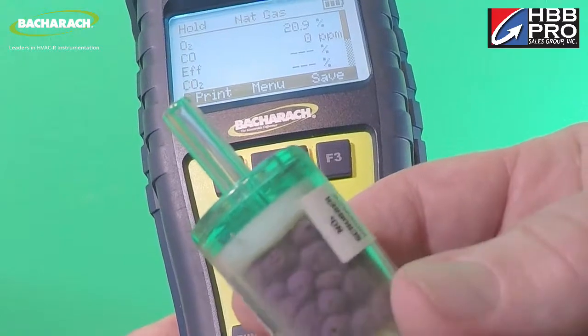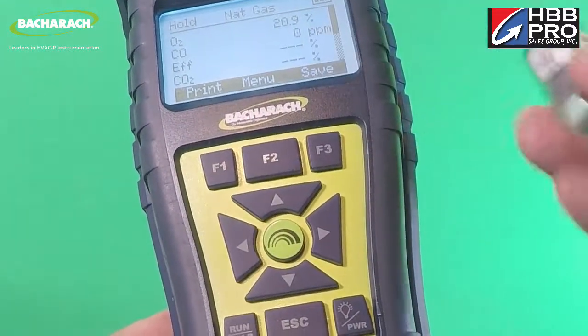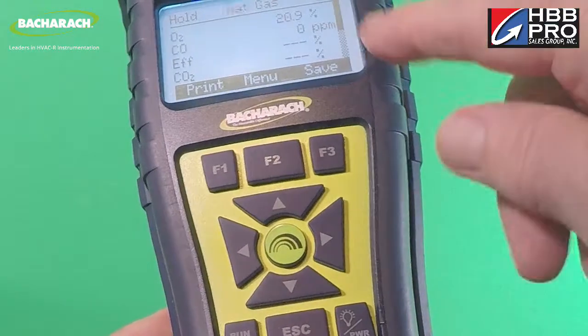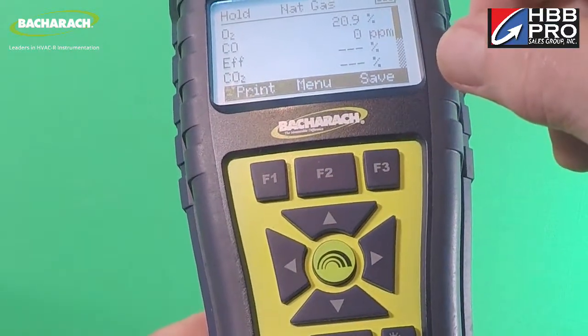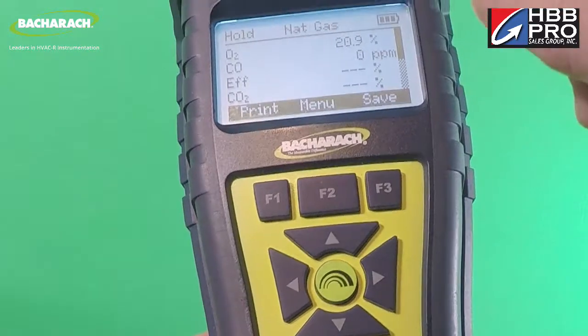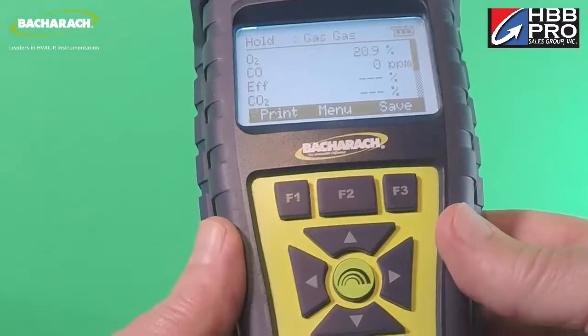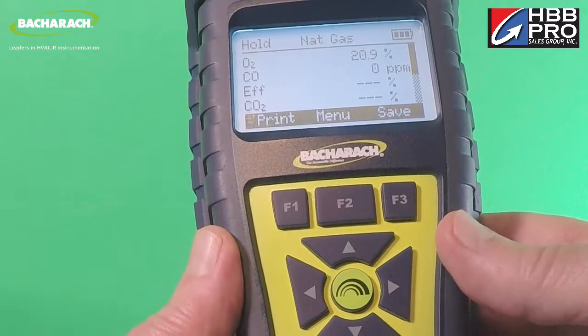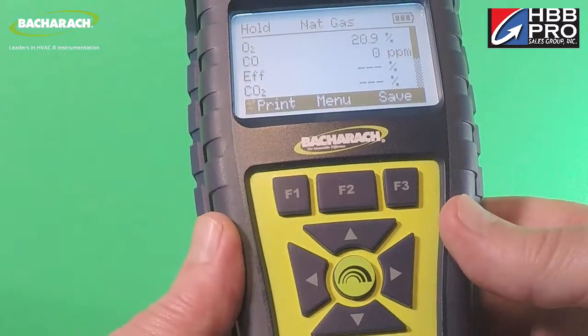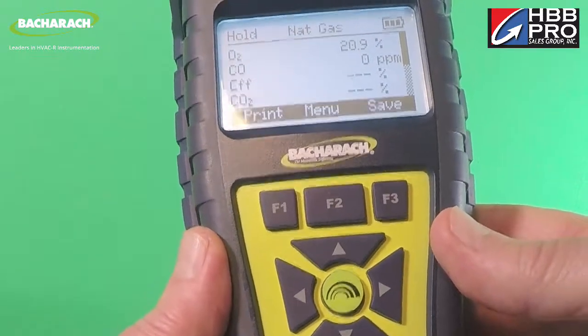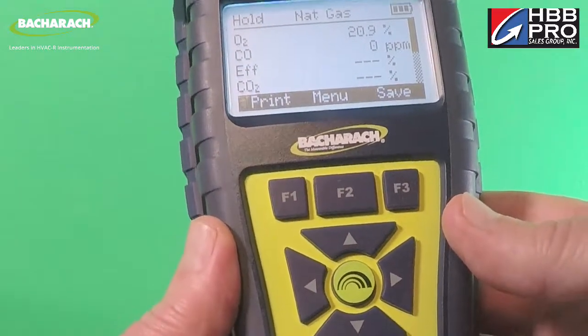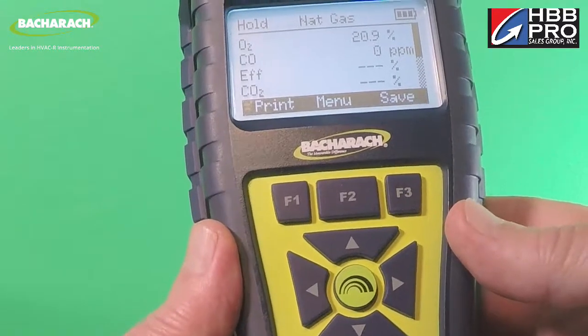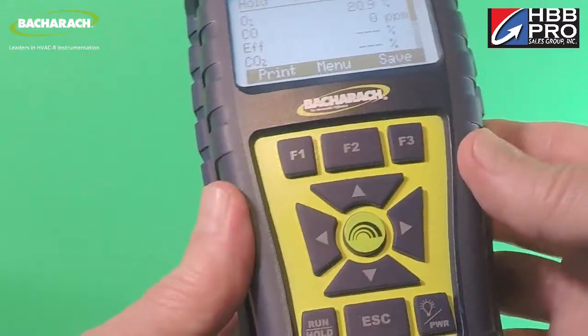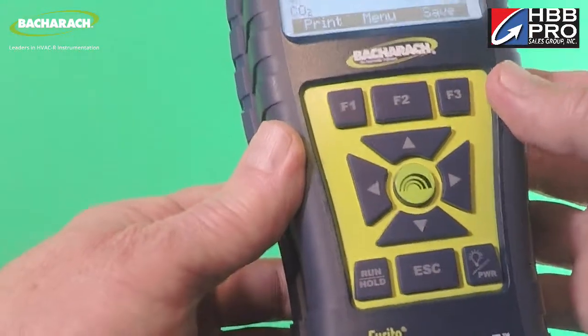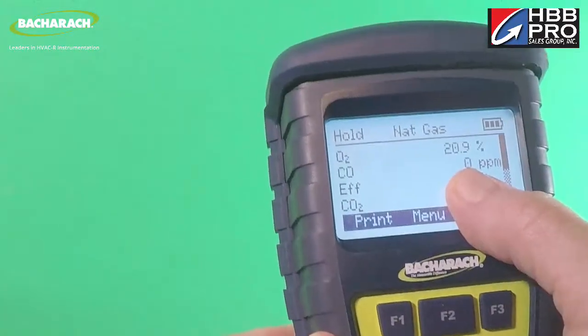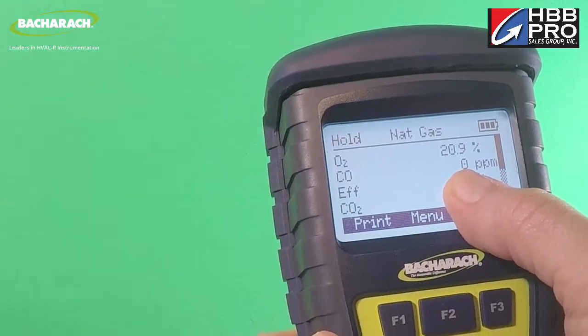Another consideration is how the CO sensor powers up. You may have noticed that this one in the display, it said CO manual 0 on the screen during that warm-up period. What that means is that at the end of the warm-up period, the sensor will display the level of carbon monoxide in the space you're in. Obviously, that's a safety feature. I'd suggest you change it. All other manufacturers do what's called a CO auto zero, and that's how Bacharach ships their instruments. An auto zero means that the instrument assumes that the air sample during the warm-up time is clean, and it will display 0 ppm in the screen when it's finished counting down.